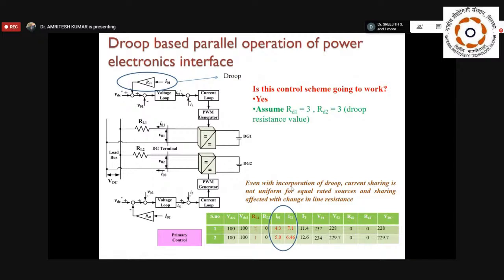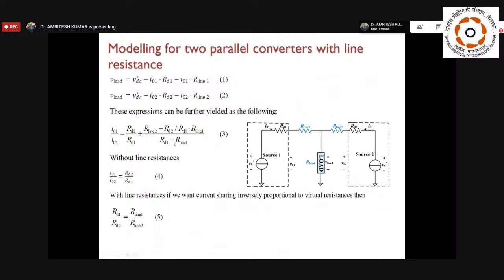So you can realize from equation 3 that if we incorporate the line resistance, and we still want current sharing inversely proportional to virtual resistance, as in equation 4, then basically we want to maintain equation 4 even though we have a line resistance. This is my major point: I want to maintain equation number 4 always, meaning current sharing inversely proportional to droop resistance.